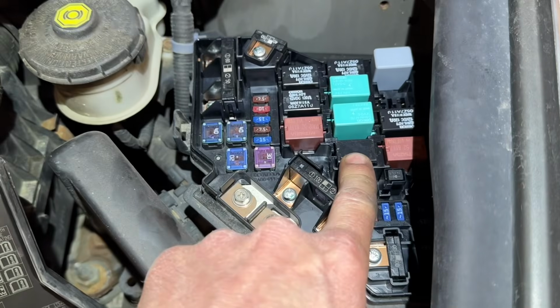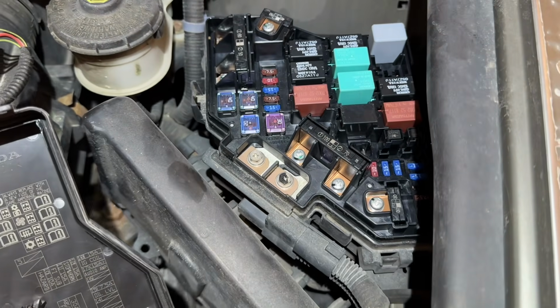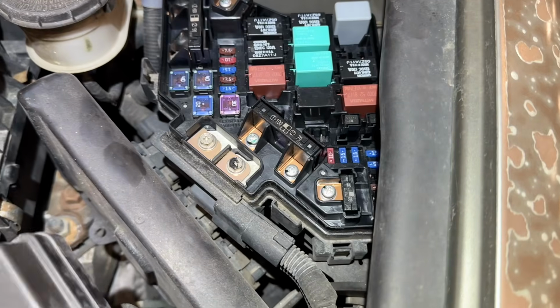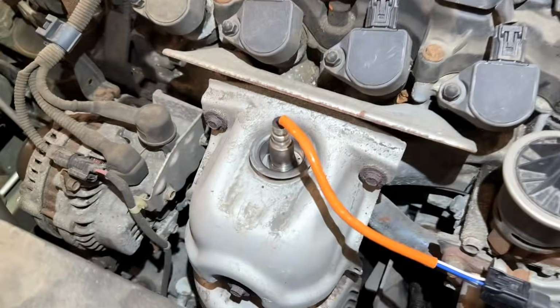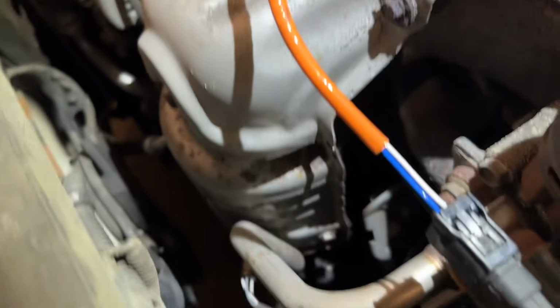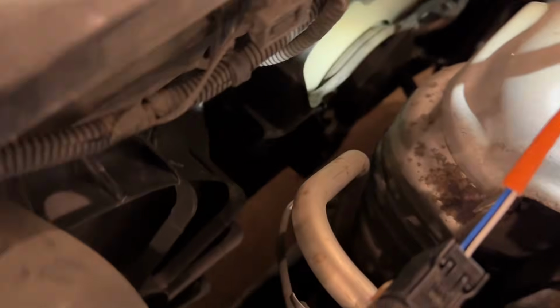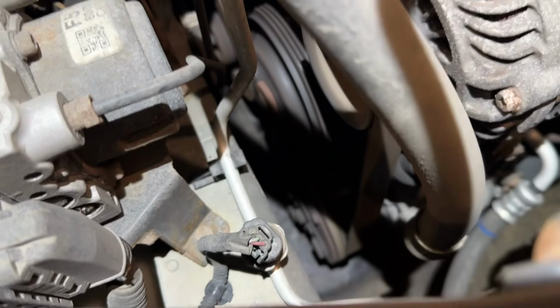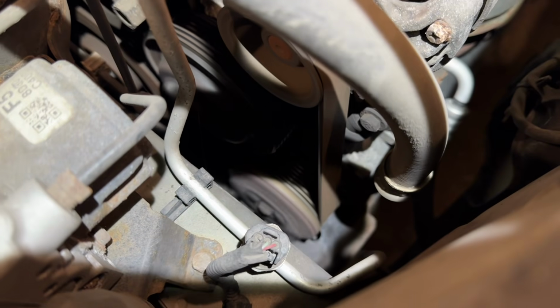So we've got our new relay installed here, so we can put the cover back on. It's been cycling a little bit here, so the cooling fans are running on low currently, not the high speed, so they're not as noisy. Our compressor is off at the moment. Try and keep the light on it, but you can see that it's cycling.